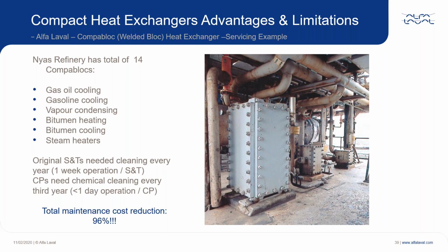Previously, the shell and tubes had to be opened every year for inspection and cleaning, and they cost almost 10,000 euros per unit, with the exception of one of the Compablocs. Our units don't need to be open for cleaning. It's all done by cleaning in place with a 3% caustic fluid every 3rd year. This operation takes less than a day, and that would cost less than €1,000 per unit. Only the bitumen heat exchanger has to be opened up every year for manual cleaning by water jet. This takes 2 days, and because it's a corrosion resistant material, the local authorities don't require an inspection.